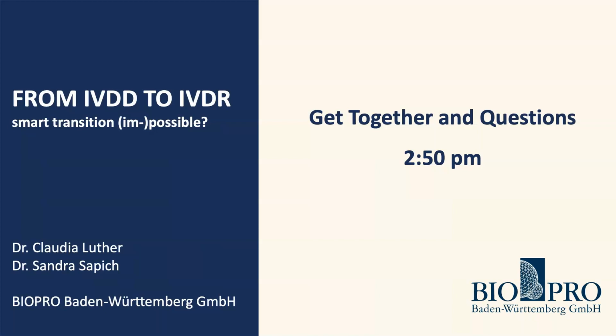for this entire discussion. And I would like to share the link to the Blue Guide in the chat. You should have a look into the Blue Guide related to those definitions, and also related to what the manufacturer means, in addition to what is the definition of the IVDR or the MDR. Because in fact, the so-called private labeling or virtual manufacturing, that's just wording. It does not really exist. You are on the label, you are the manufacturer, and you have the full responsibility.